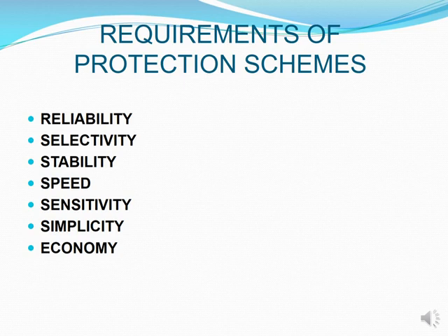You want it to clear all your faults as speedily as possible, and you want to have some sensitivity in it so that it does not clear faults outside its boundaries, but looks at the boundary that you are trying to protect. You need it to be very simple so that it's easy for the operators in the field to correct or manipulate if there are things that need to be changed. And of course, it needs to be economical because everything comes down to cost at the end of the day. If it's very expensive, then your companies will not be able to buy it, and therefore you will not have what you need.